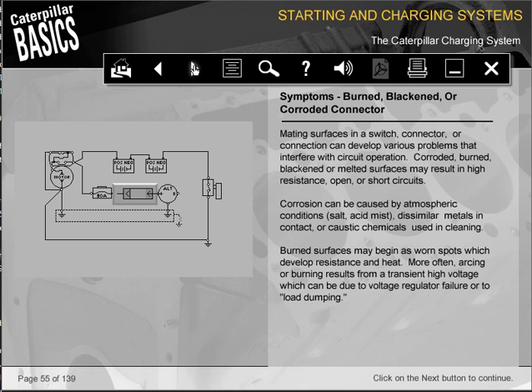Mating surfaces in a switch, connector, or connection can develop various problems that interfere with circuit operation. Corroded, burned, blackened, or melted surfaces may result in high resistance, open, or short circuits. Corrosion can be caused by atmospheric conditions, salt, acid mist, dissimilar metals in contact, or caustic chemicals used in cleaning. Burned surfaces may begin as worn spots which develop resistance and heat.